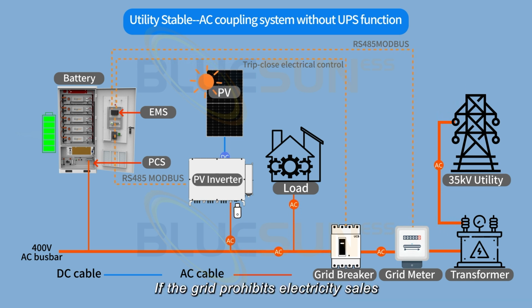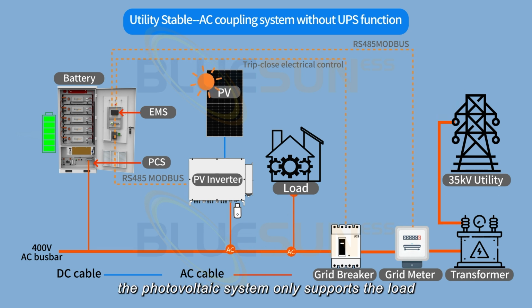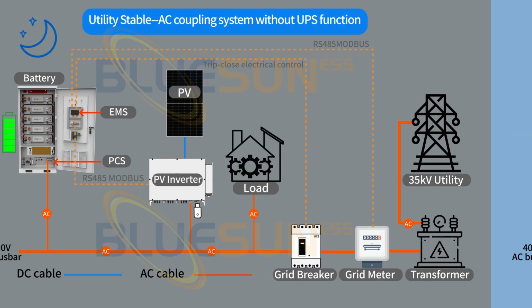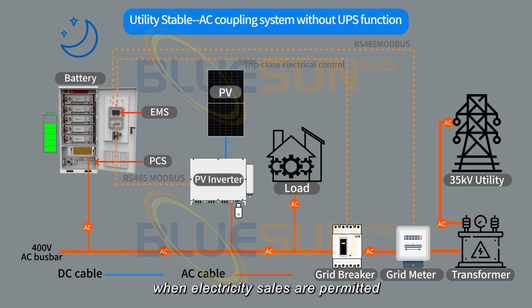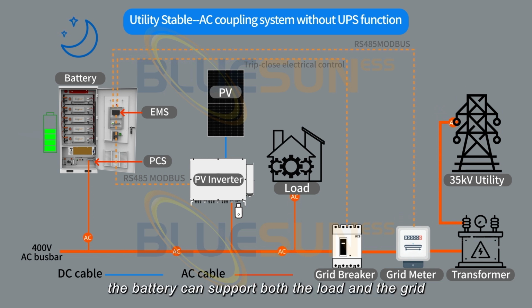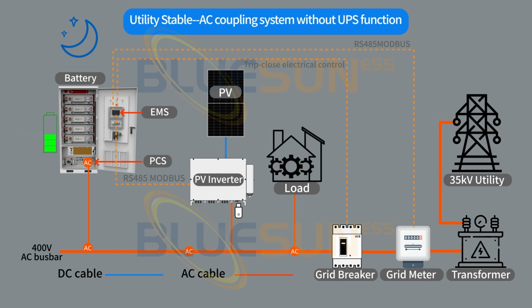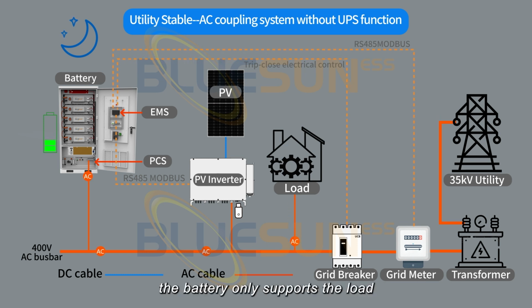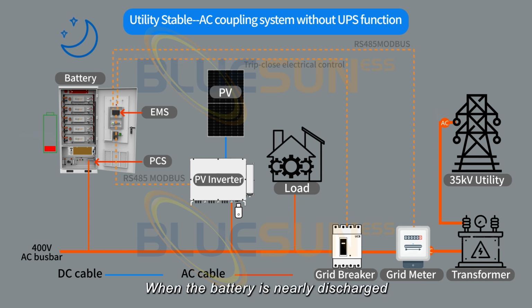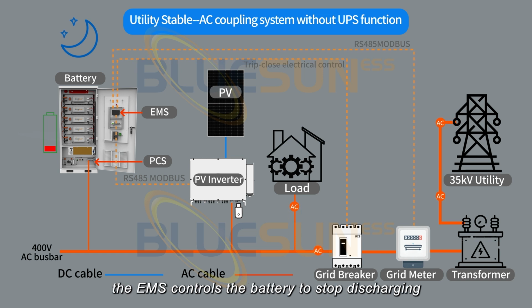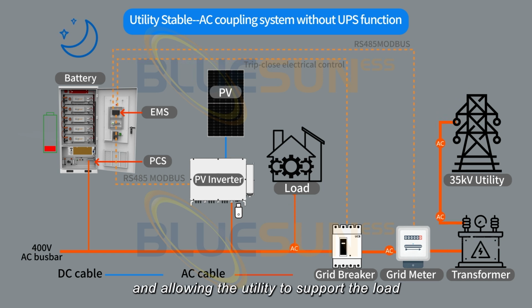If the grid prohibits electricity sales, the photovoltaic system only supports the load. At night, when electricity sales are permitted, the battery can support both the load and the grid. Otherwise, the battery only supports the load. When the battery is nearly discharged, the EMS controls the battery to stop discharging, allowing the utility to support the load.